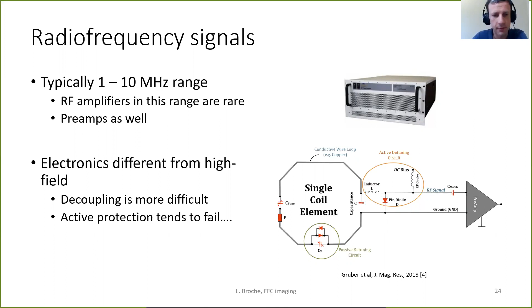At high field, that works quite well because you don't need a very strong solenoid here to block radio frequencies. When you go to low field, you need something big here, and this solenoid starts to couple with the coil itself and with the rest. So it starts to be a mess. So it's difficult to actually make coil arrays at low field. It's one of the reasons. There are others. But you have to bear in mind that there are complexities at low field that don't appear at higher fields, which is a bit counterintuitive.